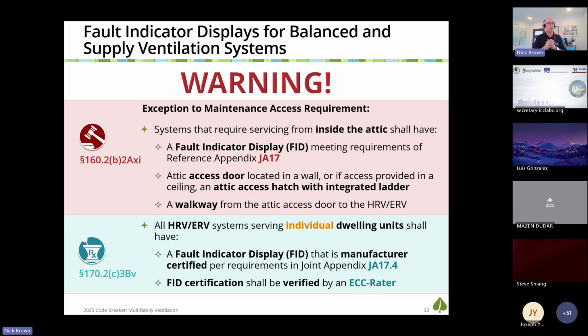Now, on the prescriptive standard side of things, if you have an HRV serving individual dwelling units, the FID gets you a little extra credit. Think of it that way. Or put another way, FID is standard, and if you leave that FID off your HRV, sorry for all the three-letter acronyms, you give up about 10% of the compliance credit in my experience running these energy models. So it's not a mandatory requirement. You see the prescriptive icon, but it is worth a little extra credit. Now, if they're complying via the prescriptive approach, they're going to have that FID with the recovery ventilator system. So two different scenarios for FIDs to come into play, one mandatory, one prescriptive.